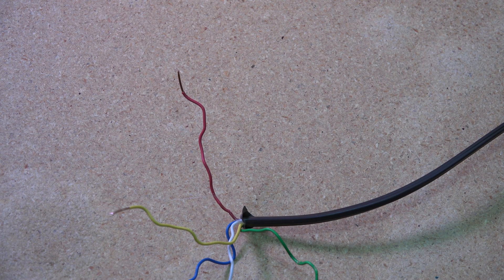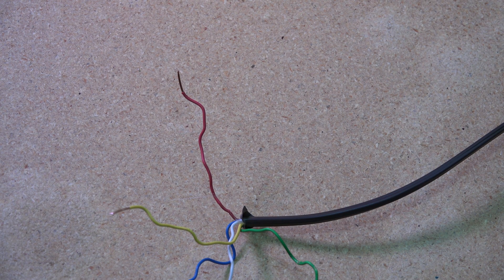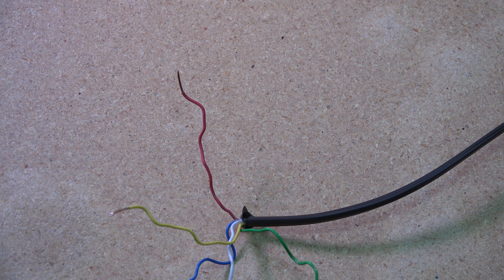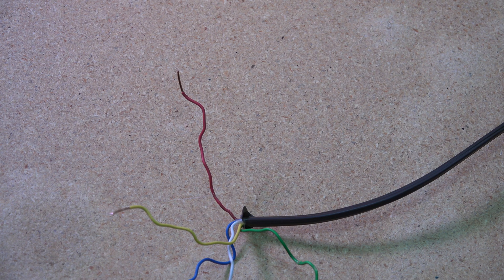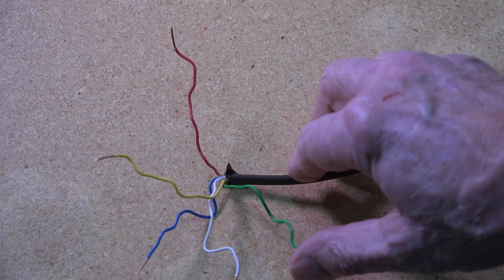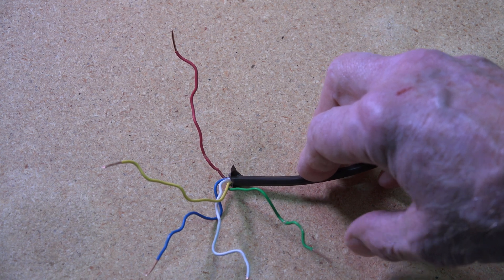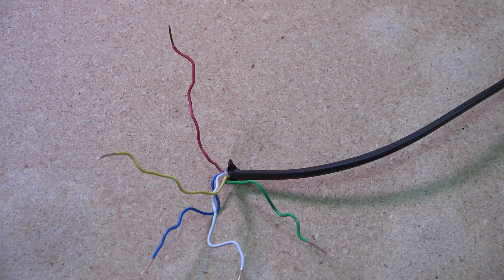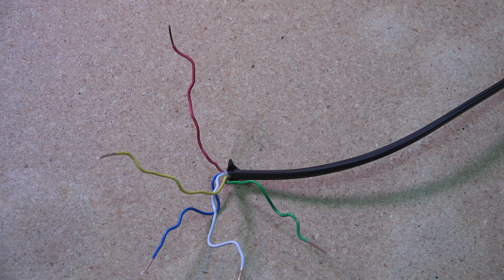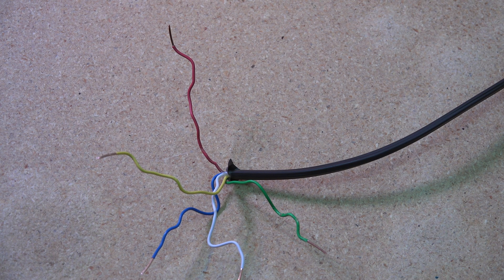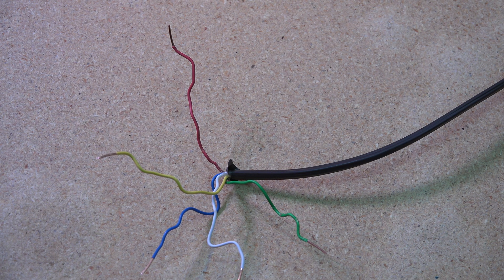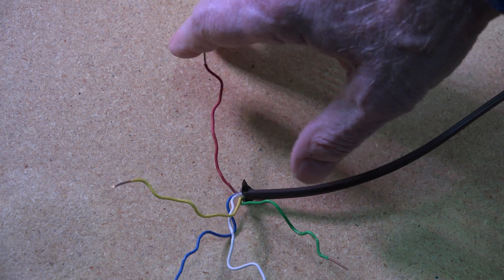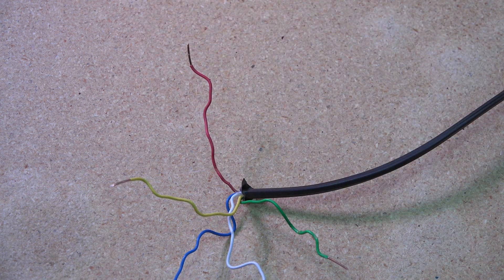Now that could be - in this case it's red, so it's probably going to be a power lead, so nothing's going to work in the thermostat. It could have been the green here and the fan wouldn't work, and so on. But this is a problem and I found this in several places.